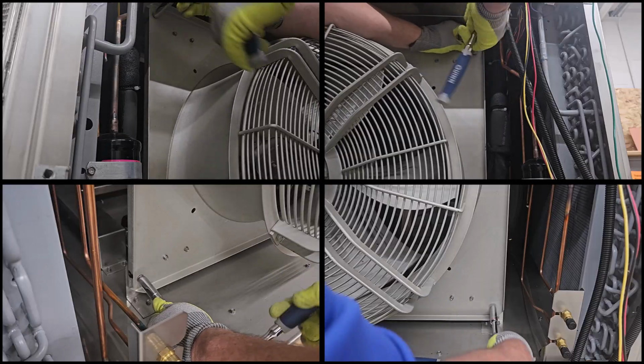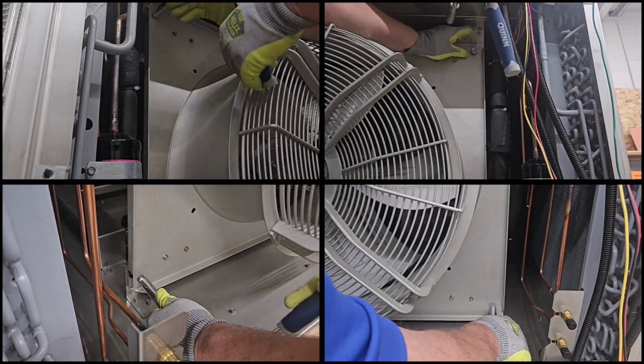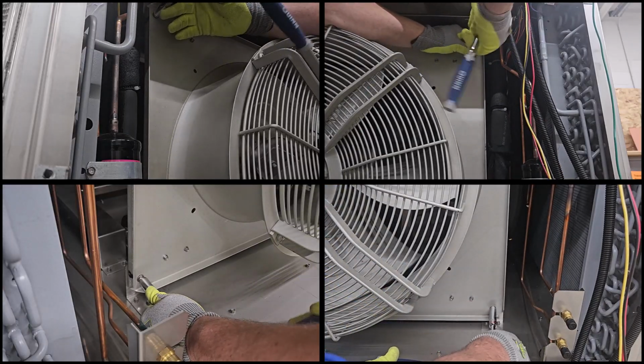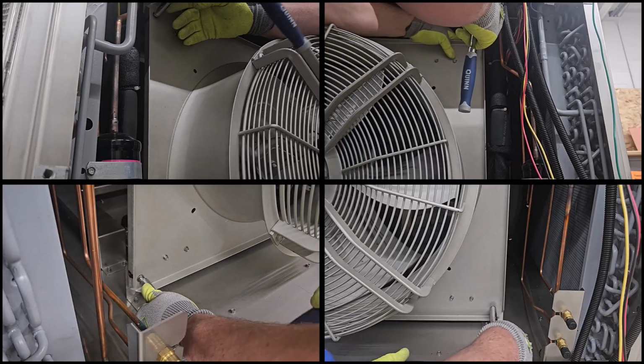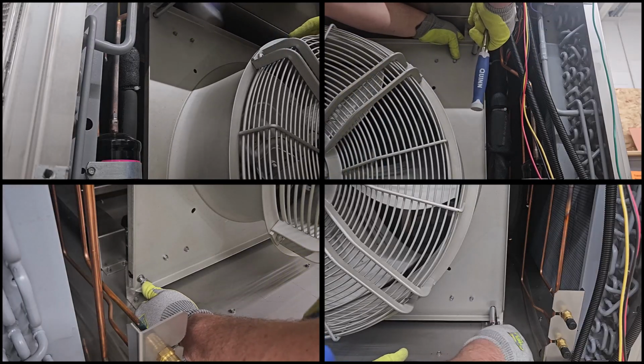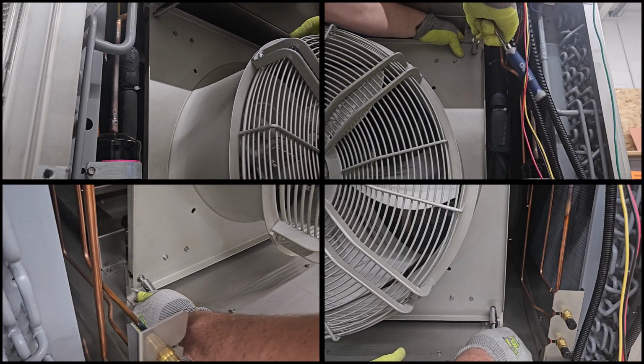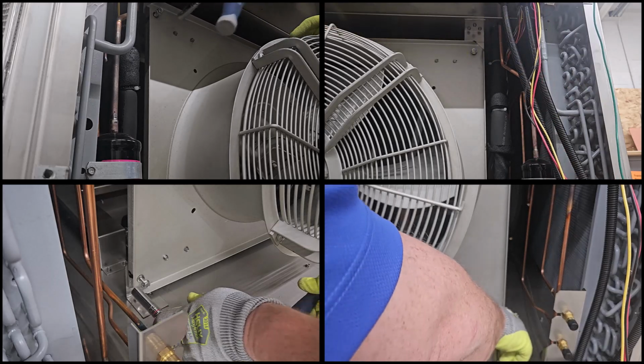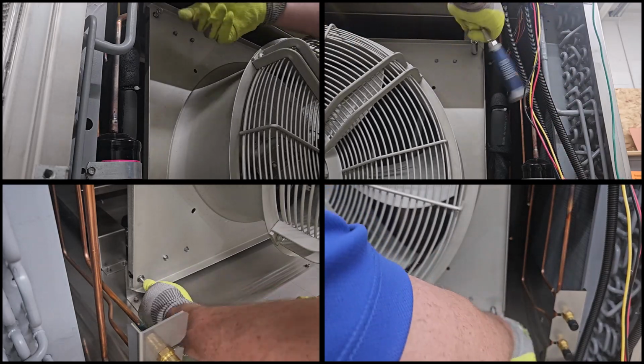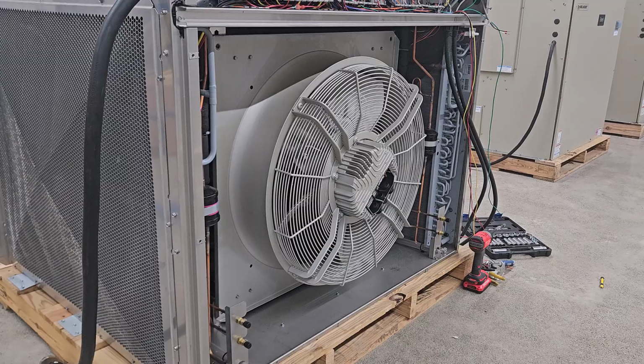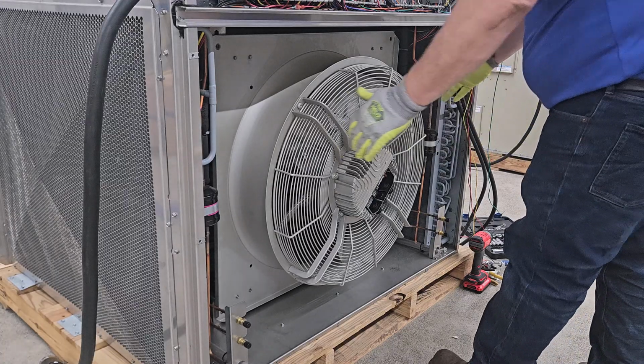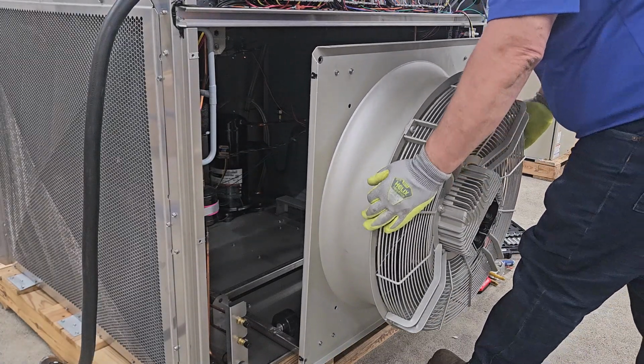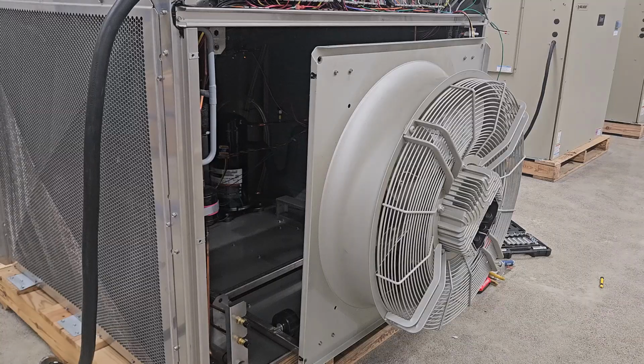A driver can be used to help speed up removal. I will caution you against using the driver when reinstalling the bolts. The chance of cross-threading the bolts increases when using that tool. I would first hand tighten and then use the driver to install. Take the motor assembly and pull it out of the condensing section of the MEGA-TEC.